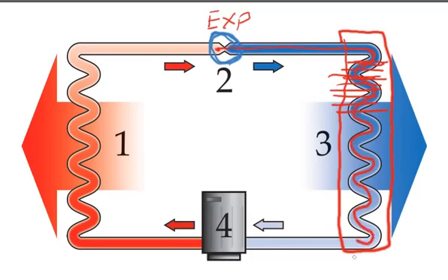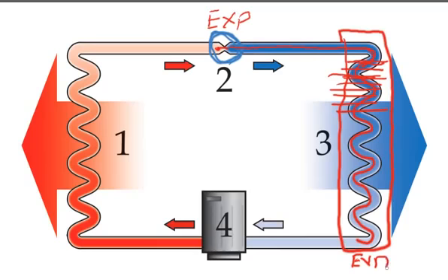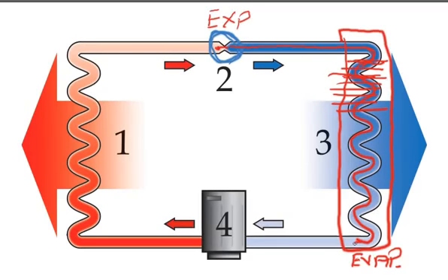So this is our evaporator coil, and the gas exits this evaporator coil and it's picked up all of this heat. So it's a gas. This line will feel cold to the touch, but it's a gas and not a liquid. So it's entering the compressor, and basically a compressor is either a piston type pump or some type of a scroll positive displacement pump. And so many times you'll hear this copper line referred to as the suction line, because it's going into the suction side of the compressor or pump.